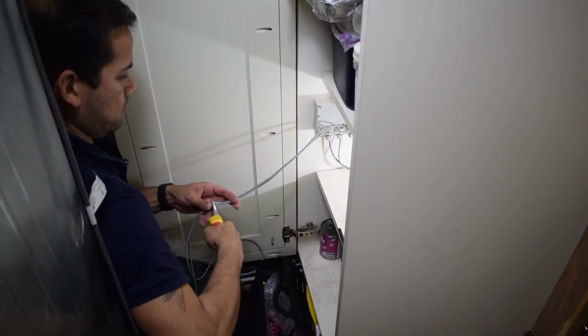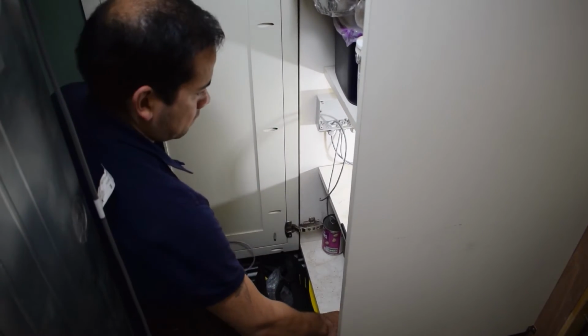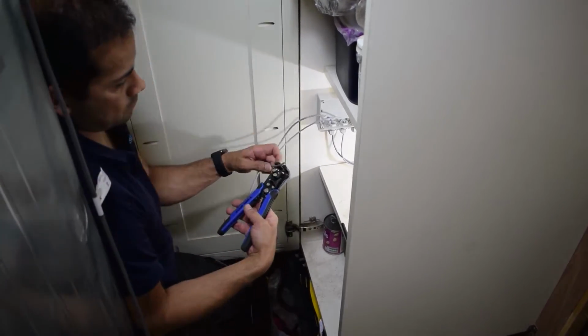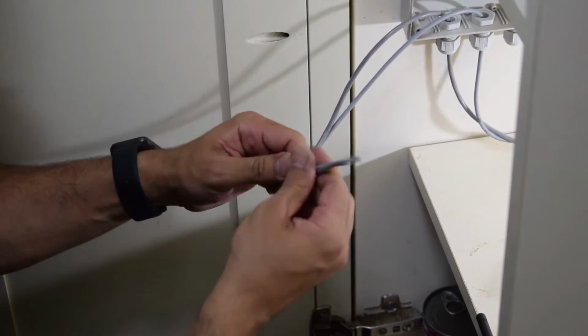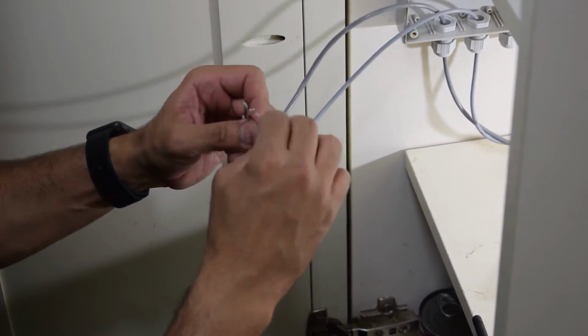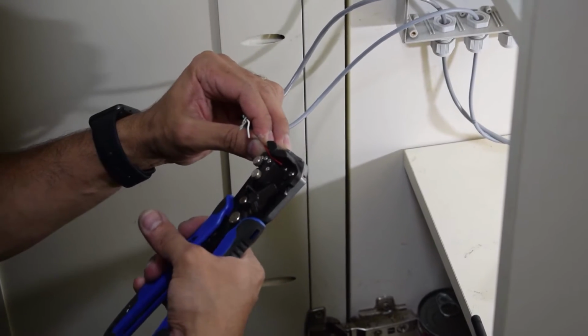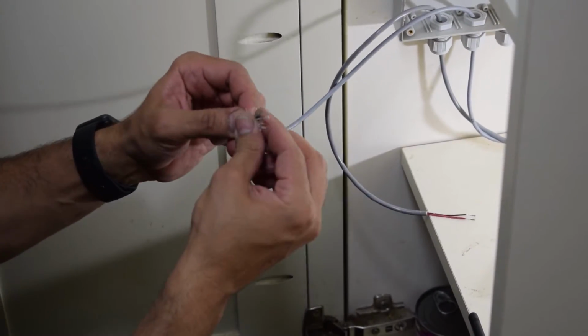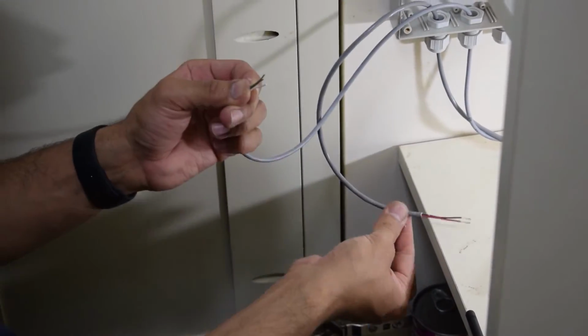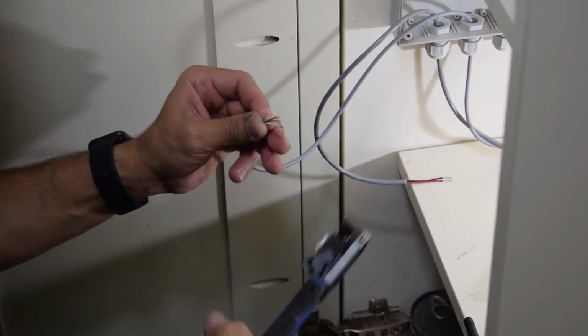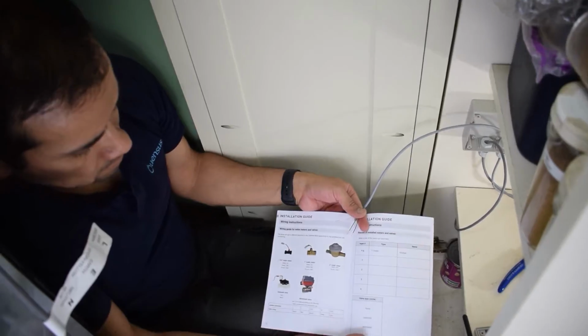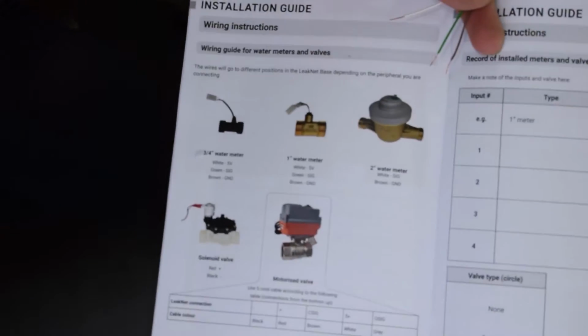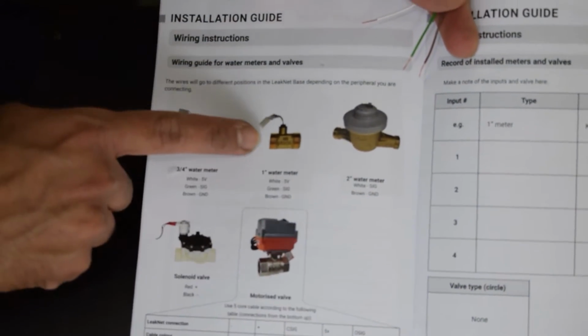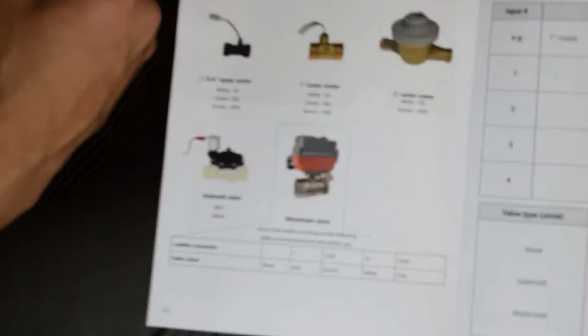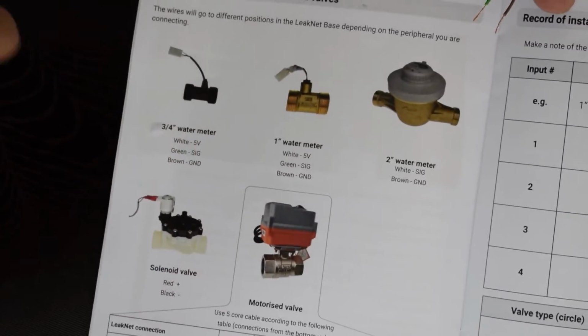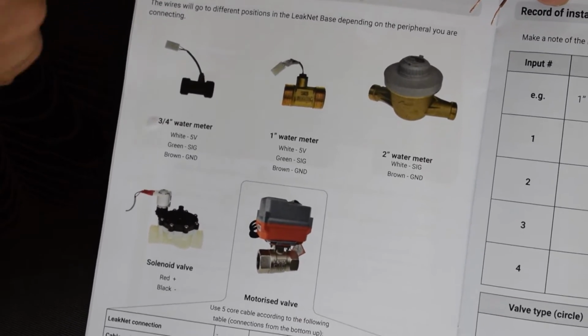So we stretched the cables, made sure they're tight just to keep it tidy, and now we're just cutting them, stripping them and cabling them into the base unit. So you don't need much to strip. Maybe about 5mm will be enough for the terminal blocks inside the base unit. So now we're cabling in, we're referring to the manual. We've got a 1-inch flow sensor and a solenoid valve. So these are the connections that we'll be fitting in: white, green and brown, red and black.